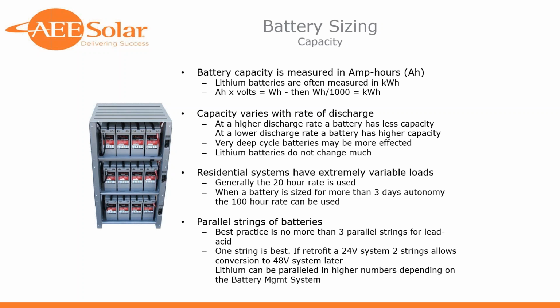But there is a little trick that if you're retrofitting a 24-volt system, if you use 2 strings, you can put all those in series later and change this to a 48-volt system, which I've known a number of people have. They want to upgrade their battery now and upgrade their inverter later, mostly for off-grid systems.